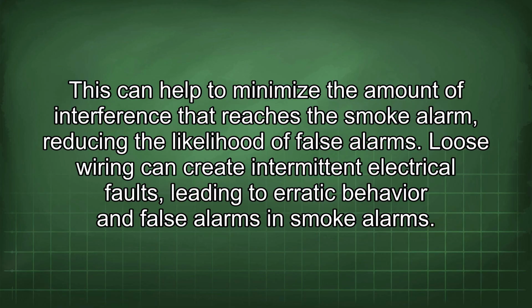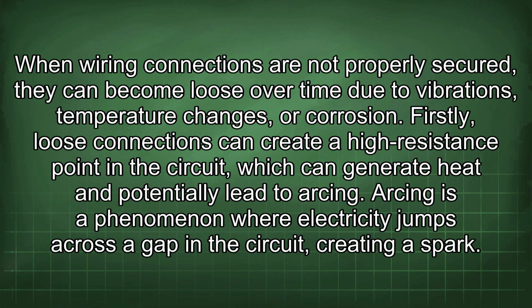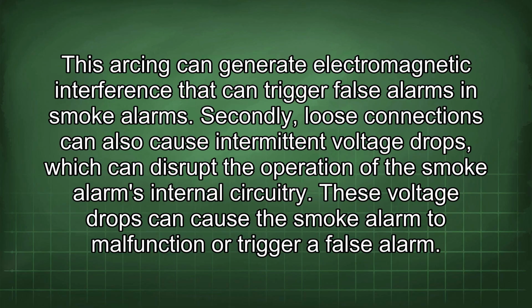Loose wiring can create intermittent electrical faults, leading to erratic behavior and false alarms in smoke alarms. When wiring connections are not properly secured, they can become loose over time due to vibrations, temperature changes, or corrosion. Firstly, loose connections can create a high resistance point in the circuit, which can generate heat and potentially lead to arcing. Arcing is a phenomenon where electricity jumps across a gap in the circuit, creating a spark. This arcing can generate electromagnetic interference that can trigger false alarms in smoke alarms.